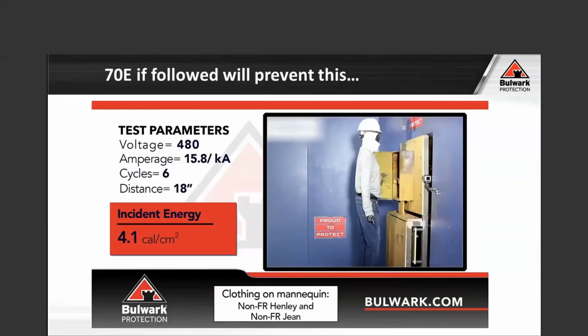So my apologies here. This is a video, and in this video, which won't play on our format today, we have a relatively low incident energy. You have 4 calories per centimeter squared. When that piece of electrical equipment faults, you see ablation of the outermost layer, which means it's actually blown away, and you have instantaneous clothing ignition, which begins to include the arms. It begins to work its way around the back, and you can see how we go to very significant injury in a relatively short period of time.